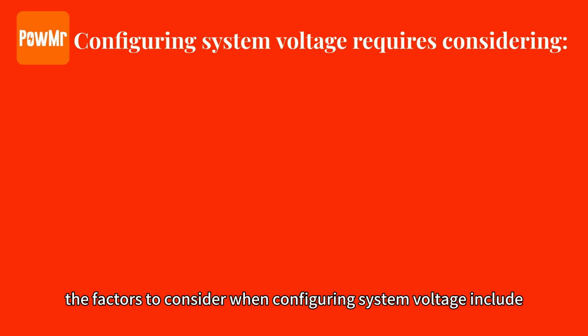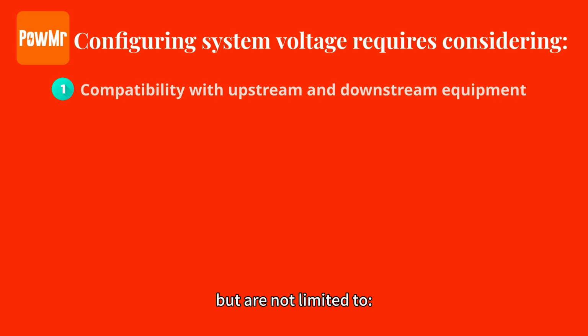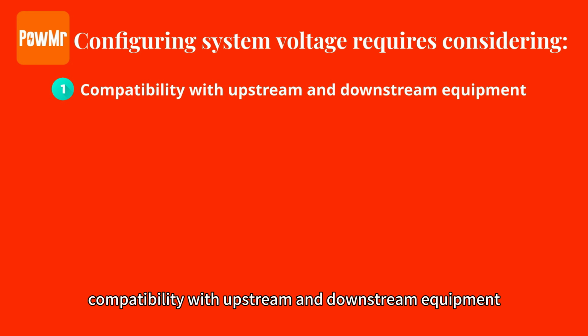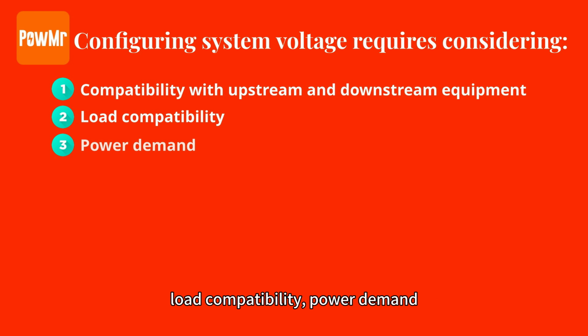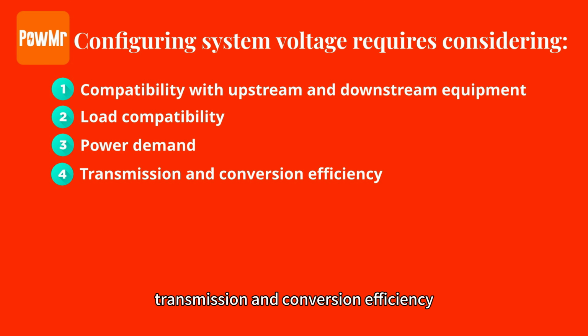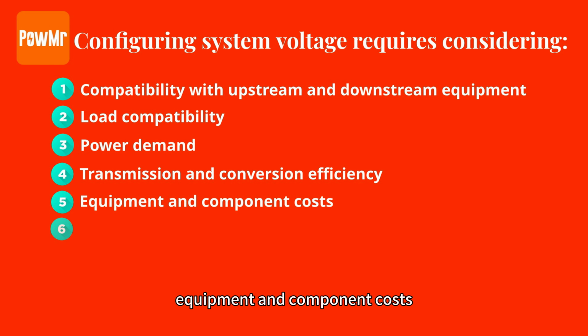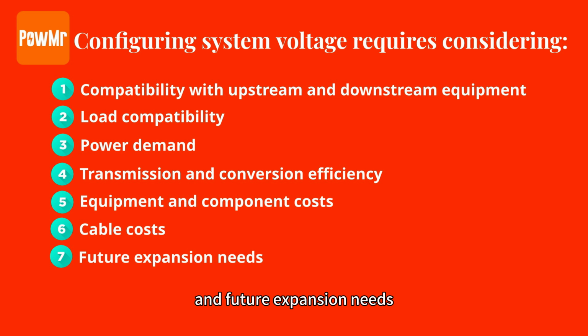In summary, the factors to consider when configuring system voltage include but are not limited to compatibility with upstream and downstream equipment, load compatibility, power demand, transmission and conversion efficiency, equipment and component costs, cable costs, and future expansion needs.